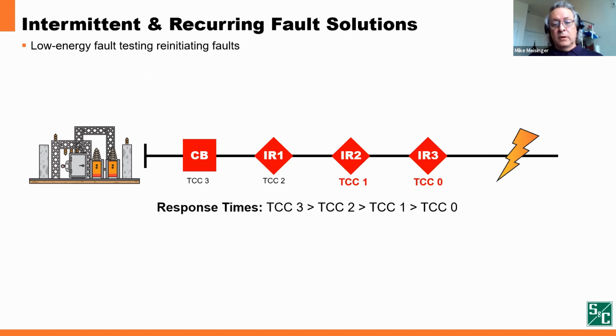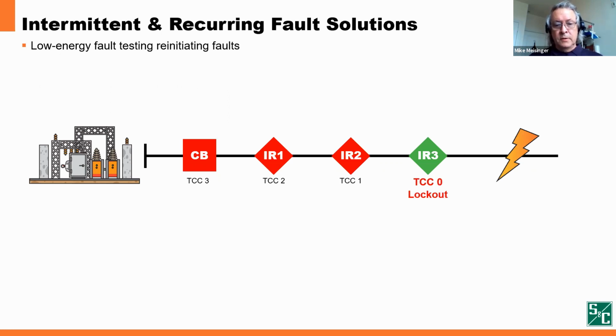IR3 then is going to close with this fastest TCC. The fault path will redevelop. Next slide. And IR3 and only IR3 will clear the fault. And that's because we've introduced coordination to this sequence of operations. Next slide, please. And eventually IR3 will lock out. Next slide.